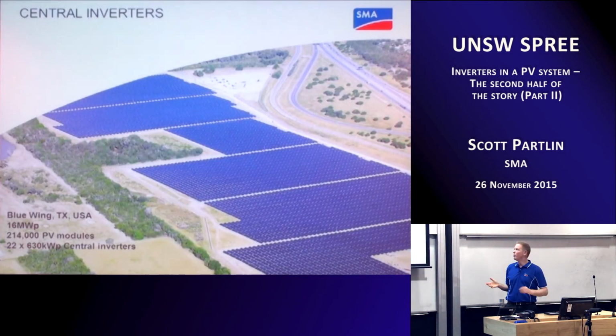And then you get to really, really big solar systems, yeah? And that's where you start using central inverters. So just as there was a sweet spot in size between a microinverter and a string inverter, that same sweet spot starts to happen with string inverters and central inverters. You wouldn't want to have a 16 megawatt plant with string inverters because you're going to have hundreds and hundreds of inverters out there, and the statistical likelihood that they're going to fail and the fact that you then have to go find them becomes a cost or a risk that you can't accept.